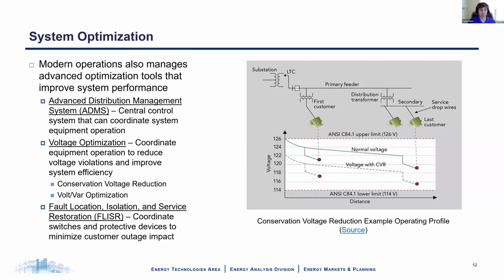Voltage optimization aims to coordinate cap banks and regulators to reduce the number of voltage violations and improve system operating efficiency. This is a combination of two different concepts: conservation voltage reduction, which is the idea that at lower voltage, things operate more efficiently. So lowering the voltage is part of optimization generally. And then volt-var optimization, which tries to reduce the amount of reactive power flow through equipment and reduces the losses as a result. So that's voltage optimization, and it's an application that can be run through this ADMS.